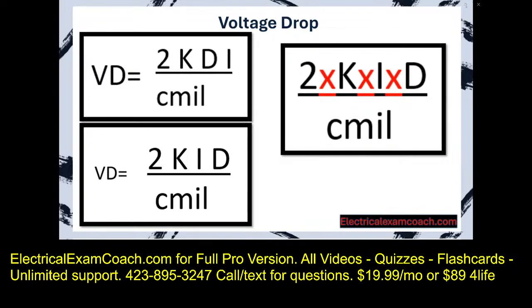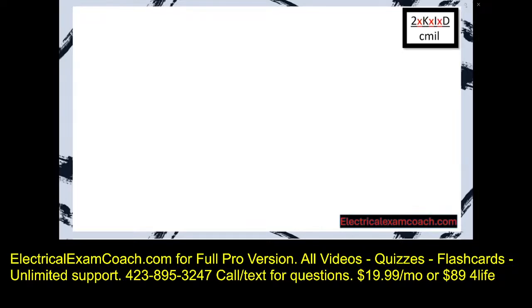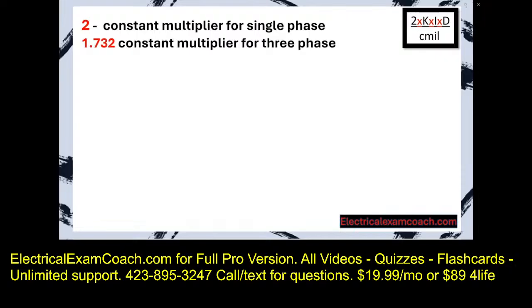So it's going to be 2 multiplied by K, multiplied by I, multiplied by D, divided by C mils. Now let's learn what each one of these individual pieces mean. 2 is going to be our constant multiplier for single phase. If we're doing 3-phase, we're going to use 1.732 as our multiplier.